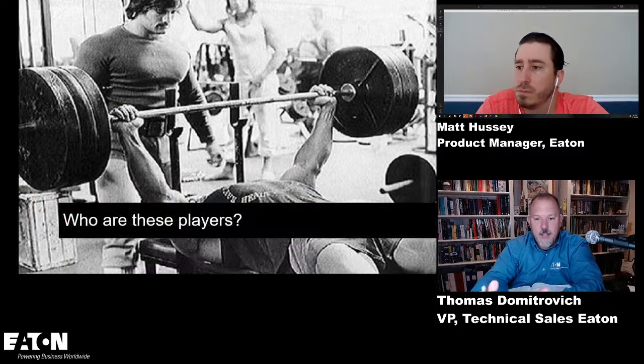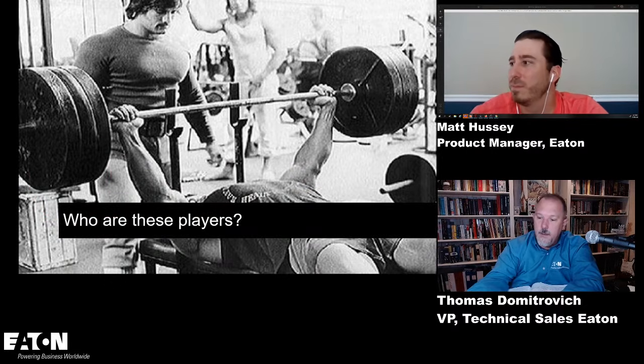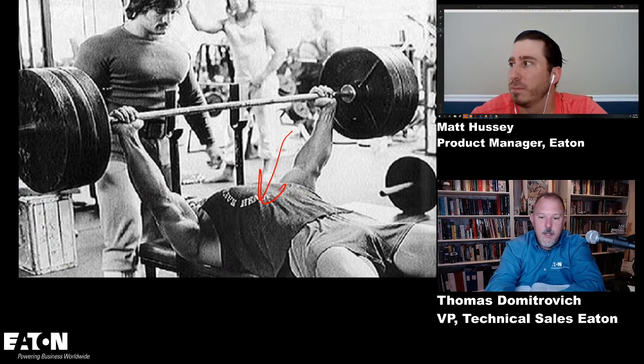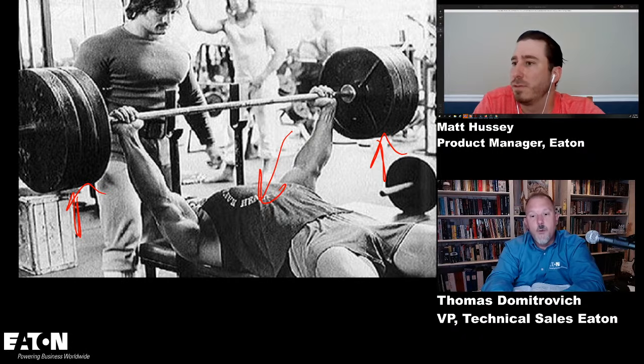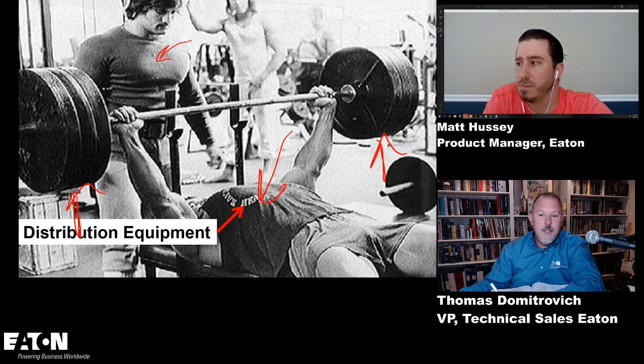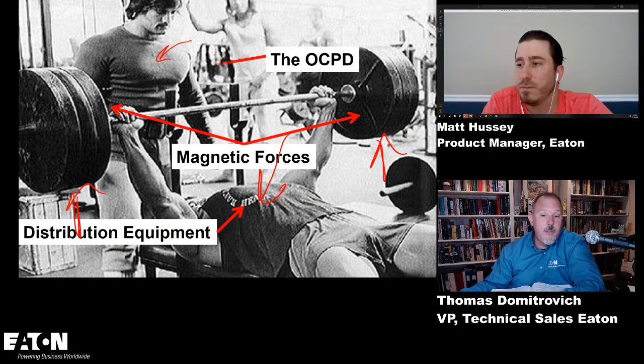And I relate this to my weightlifter example, meaning that this guy here is the electrical distribution equipment. The weights over here are the magnetic forces pressing down on it. This guy here is your spotter, and the spotter is basically there to make sure that the distribution equipment doesn't get hurt, right? And that's the overcurrent protective device. So the key thing that you got to think about from a short circuit current rating is that equipment has to be able to withstand it.